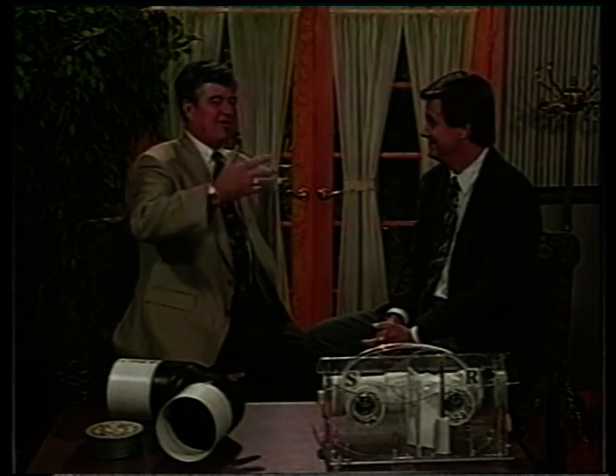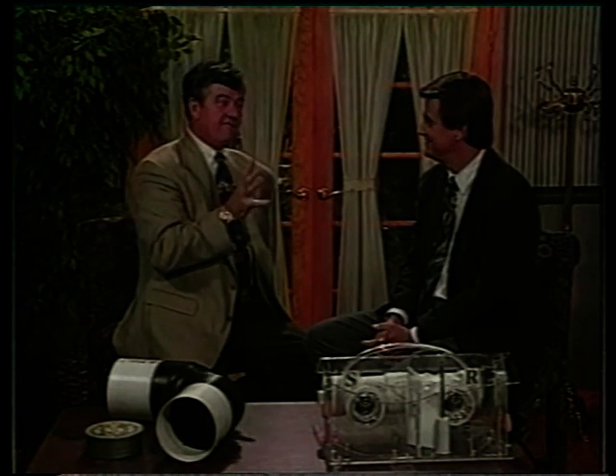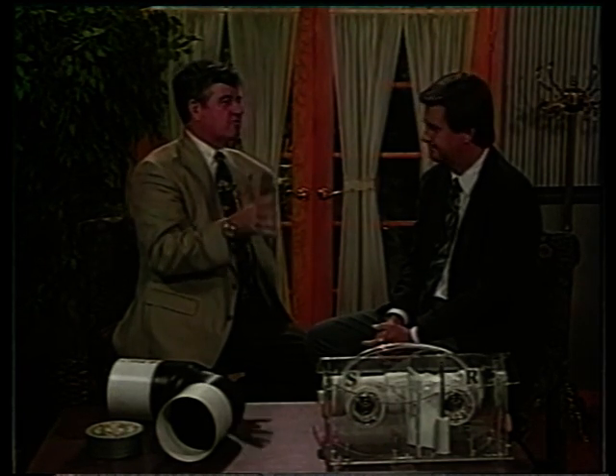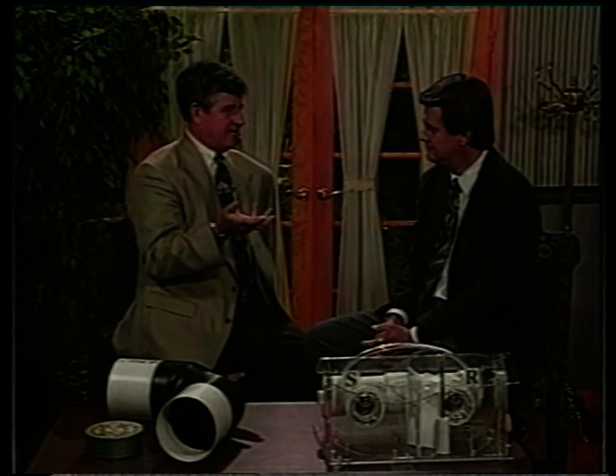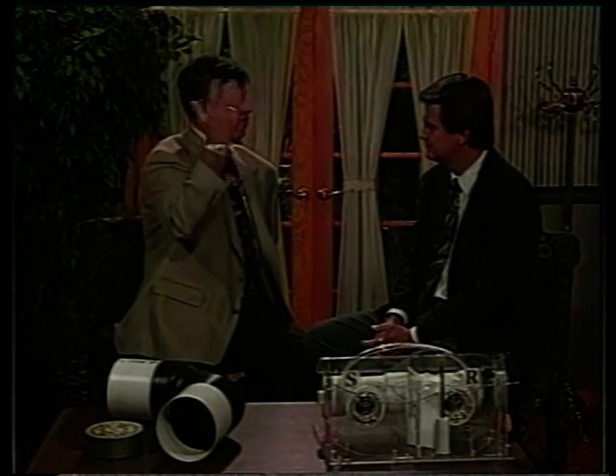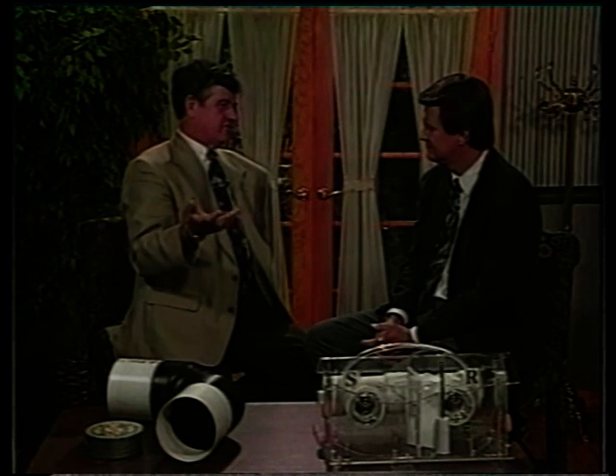I don't know. Well, the fact that your ductwork's up there, even if it's perfect — which it isn't — means you're losing 20% of your cooling to the attic today. And in the wintertime, you're blowing hot air through a cold attic. Look how serious that is.